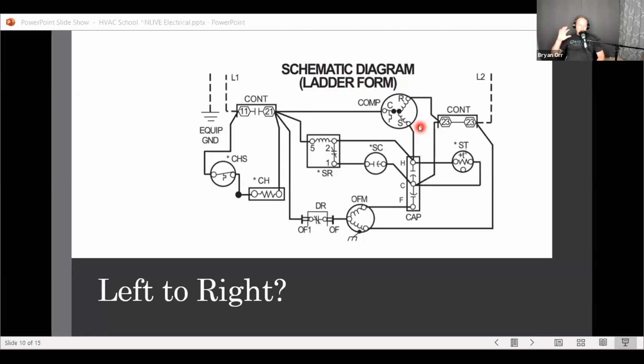And so the problem is, this is where the rubber meets the road. A lot of technicians will measure from leg to leg and see these very low resistances and think that the compressor has failed, especially if they use one of those megohmmeter things and connect leg to leg. That's a misunderstanding of how those things are supposed to work. Those are always to go to ground. So when you're checking for shorts, you're generally checking to ground.